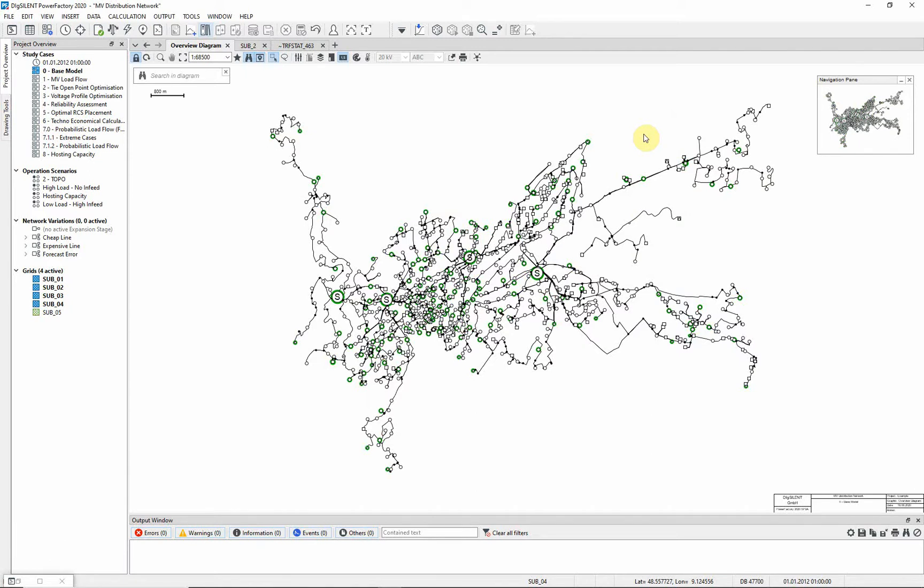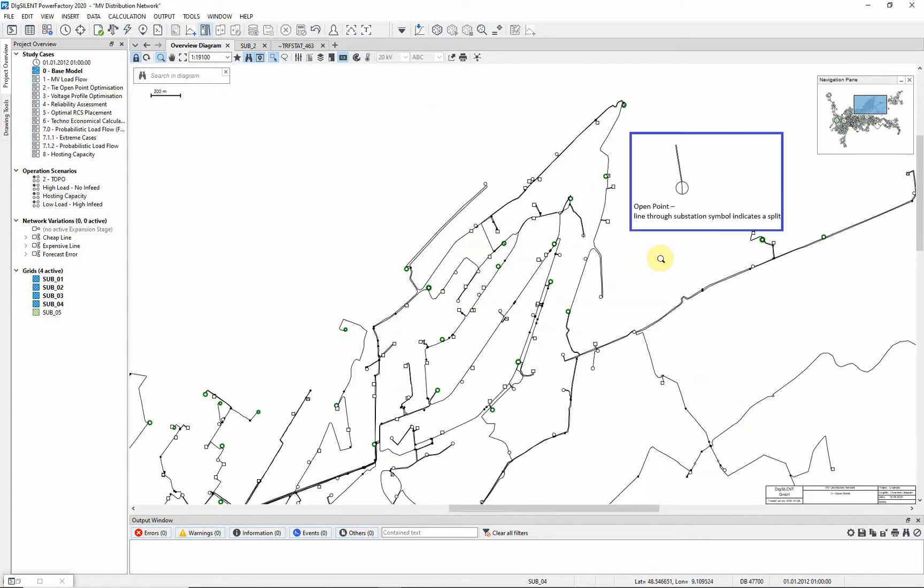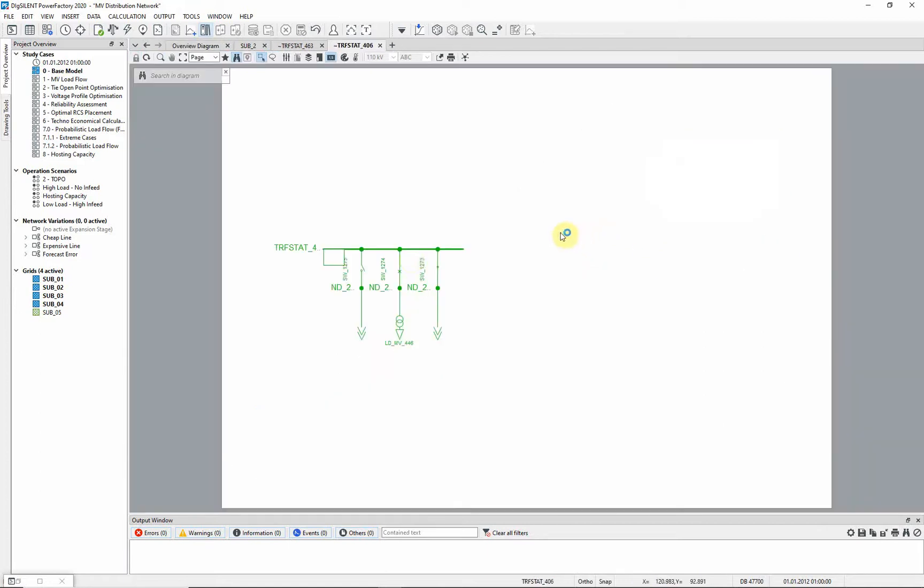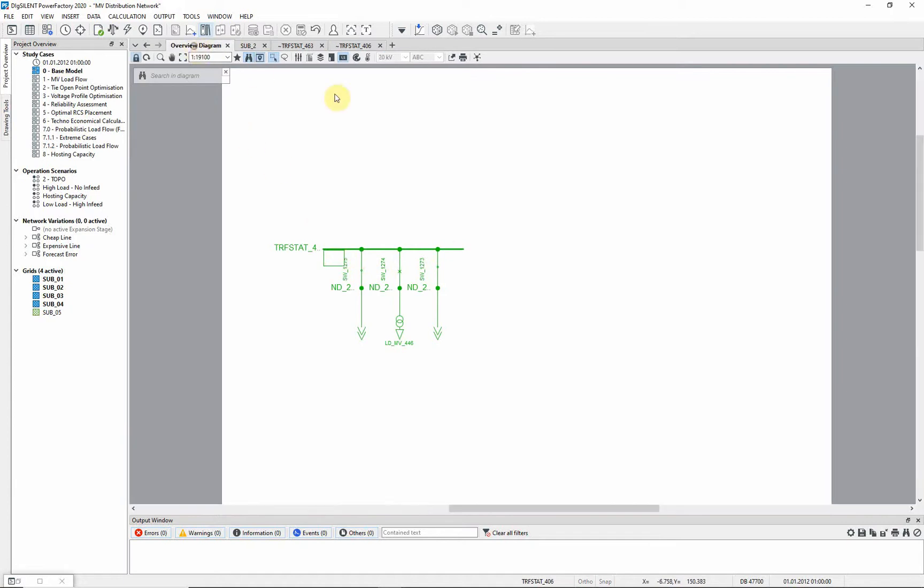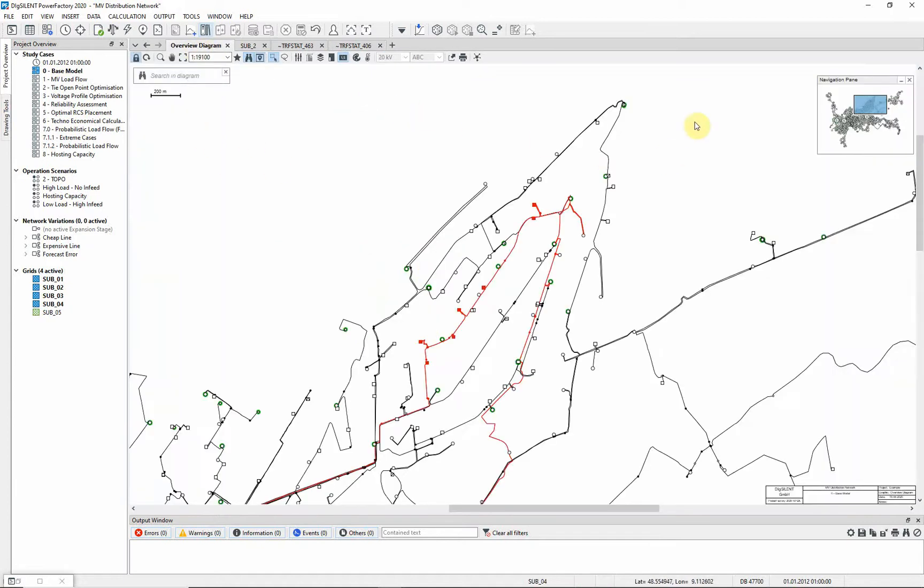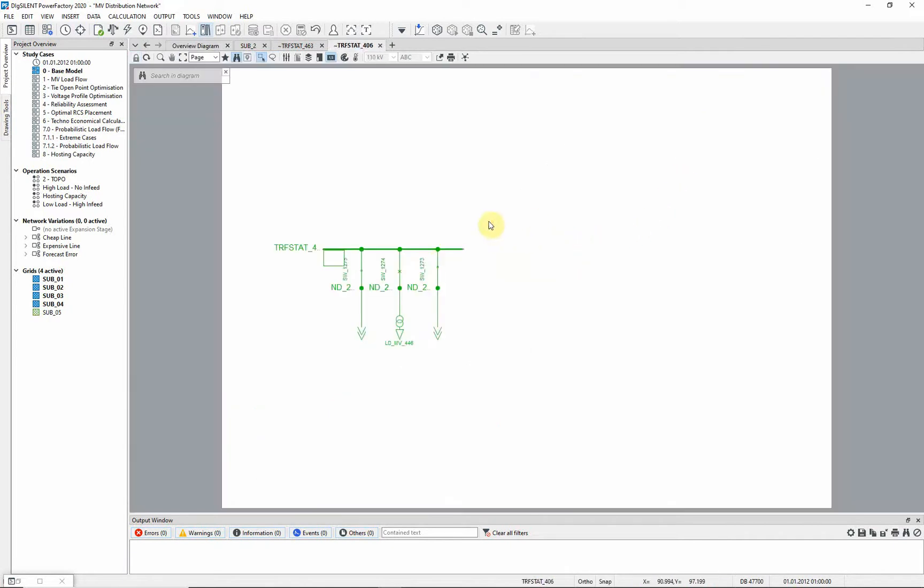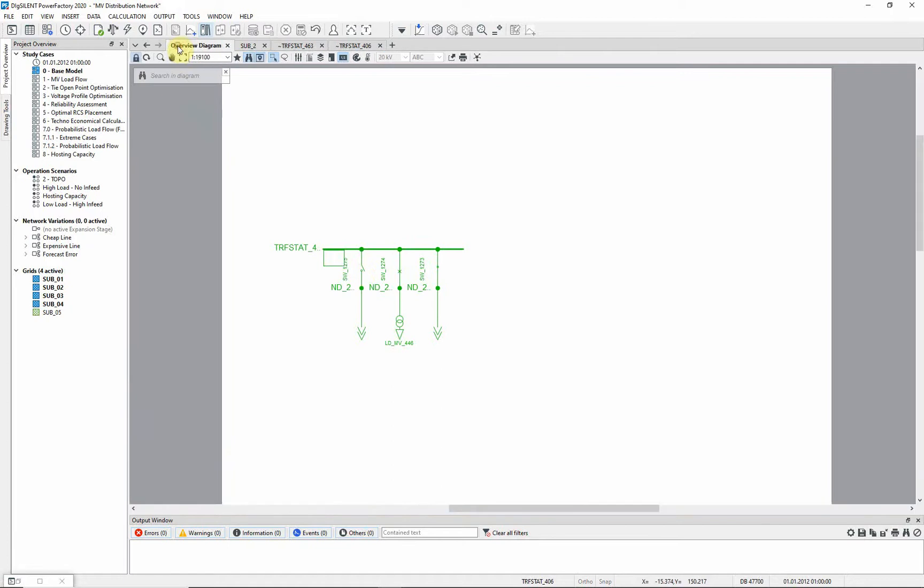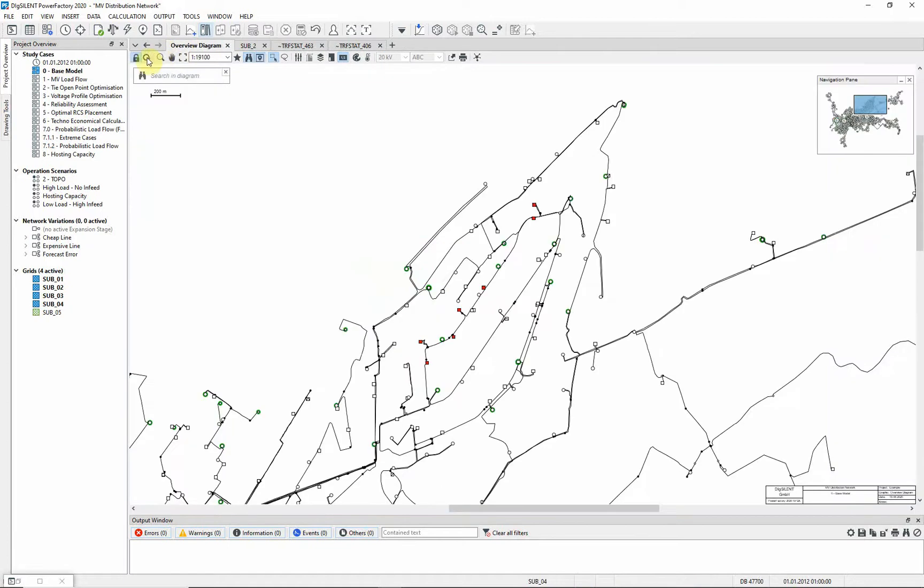Let's switch the network to deliberately introduce a ring and see what happens to the diagram coloring. Find a distribution substation with a normal open point and close the normal open point. Returning to the overview diagram, you will see that the diagram coloring of the feeders has changed to illustrate the alarm condition. Re-open the normal open point and the alarm condition will disappear.